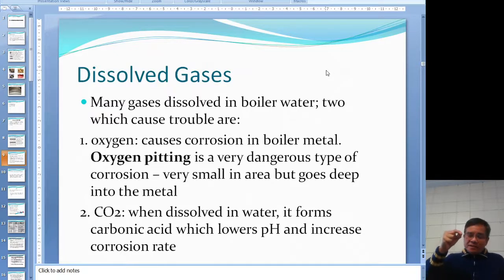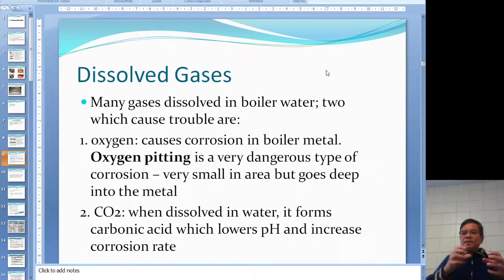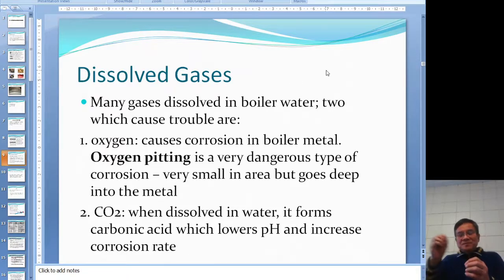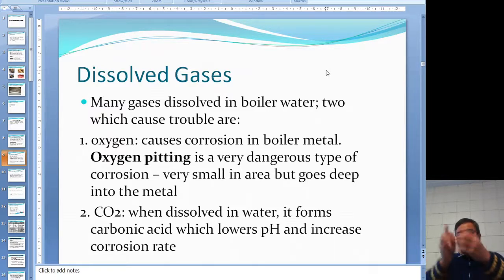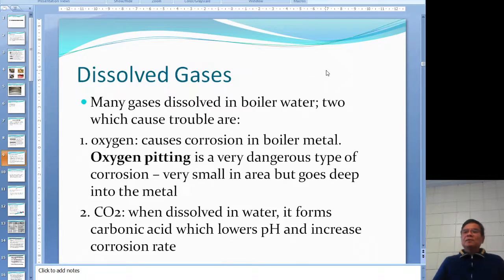Even a small hole from oxygen pitting is dangerous. If there is any hole in the tube, the pressure inside the boiler will do the rest. Steam escapes through the small hole, expanding rapidly, and more steam rushes through the same hole — the whole thing rips apart. Even a tiny hole from oxygen pitting will rip the boiler tube apart.